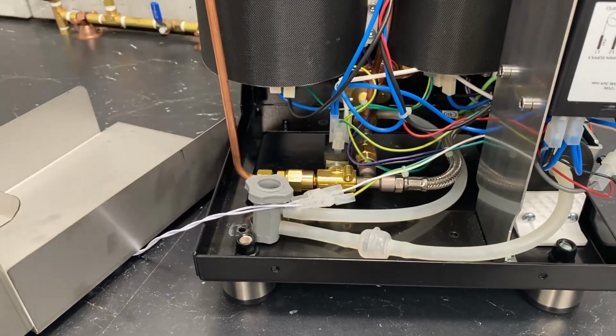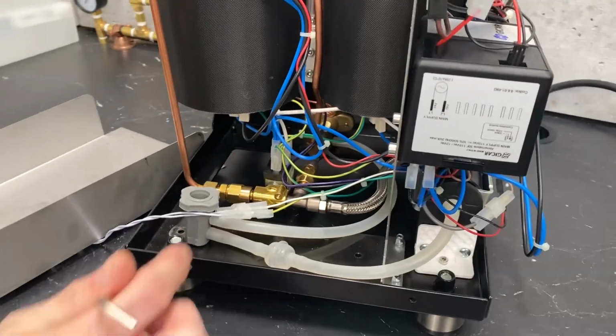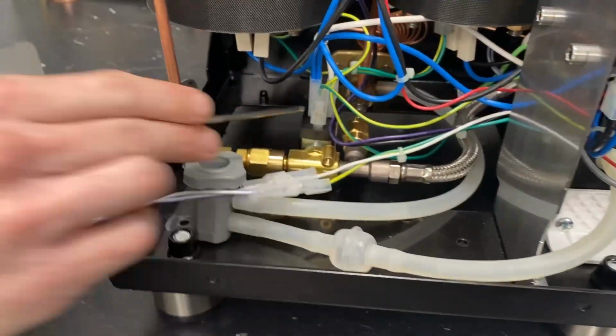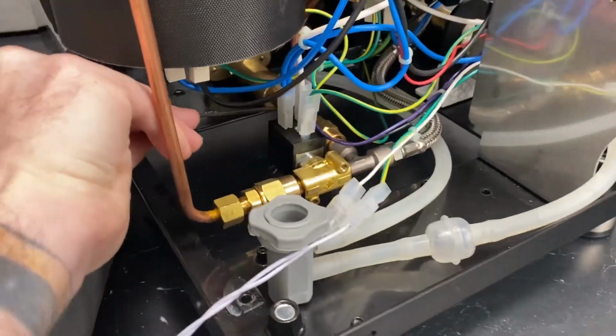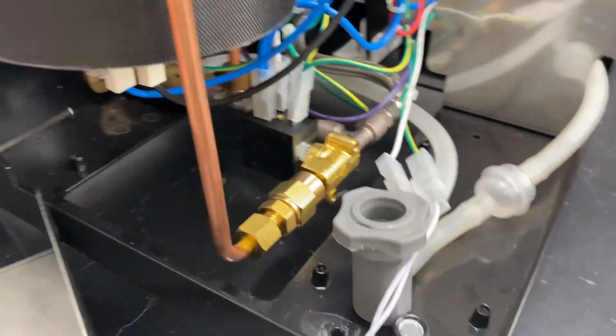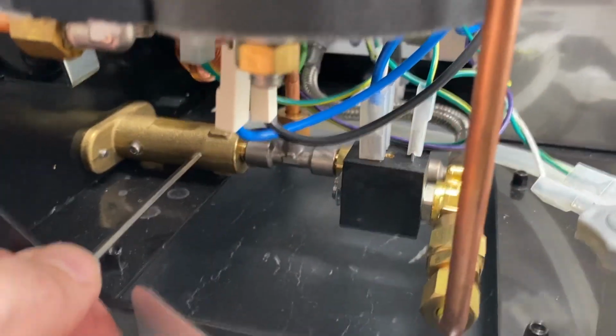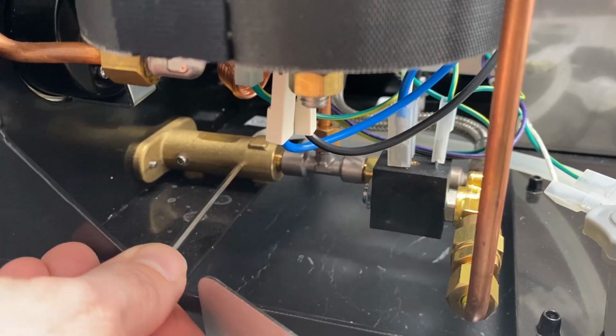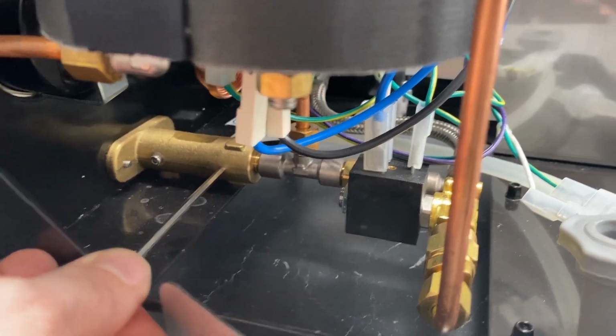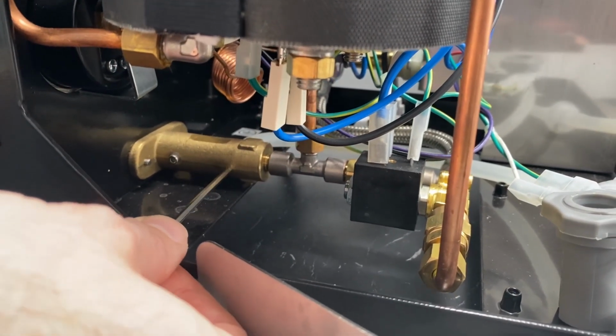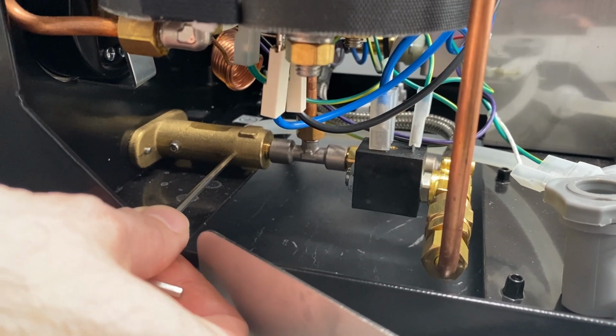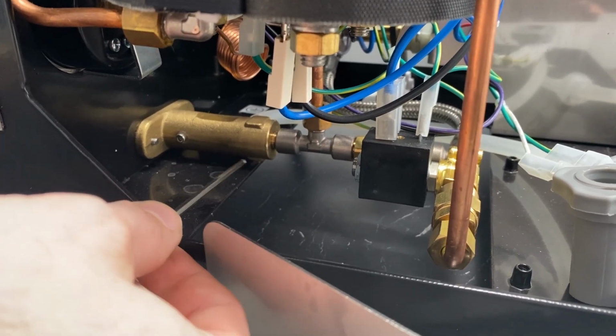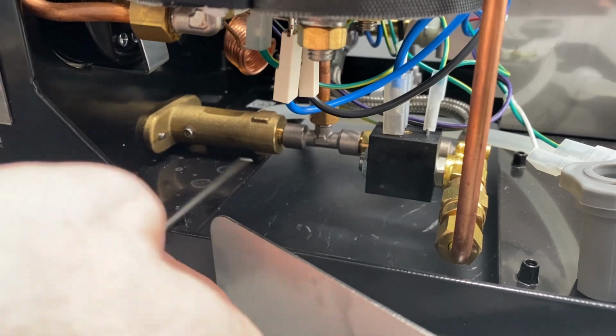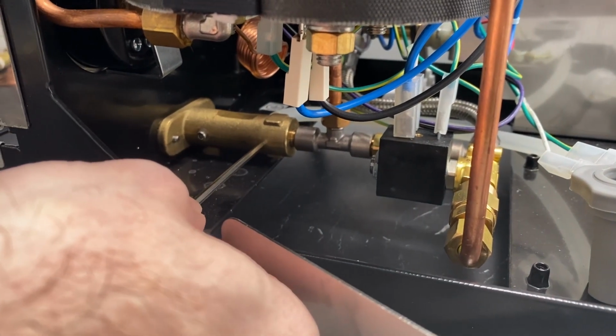Okay, so right off of that, you're gonna hit another T here. Straight ahead from the T is your overpressure valve, or OPV. This is what you use to adjust the pressure in your system. Since there is no adjustable pressure on the vibratory pump, this is what serves that purpose.